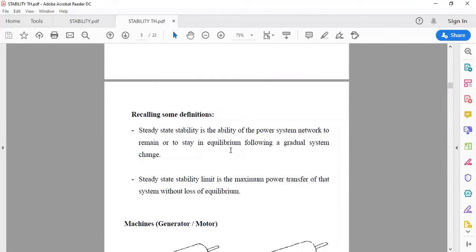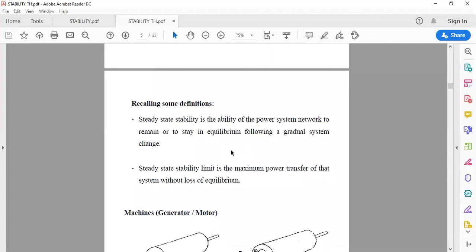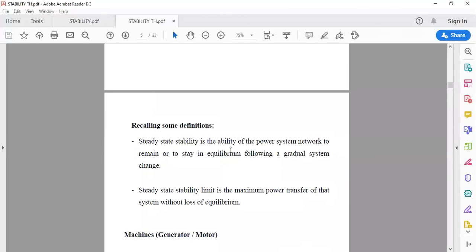Steady state stability is the ability of the power system network to remain in equilibrium following gradual system changes. The steady state stability limit is the maximum power transfer of the system without loss of synchronism. In summary: when the disturbance is of less magnitude and longer duration, it is a steady state disturbance; when the disturbance magnitude is very high and duration is very short, it is a transient disturbance.